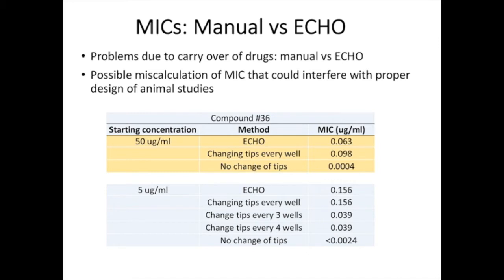And that can be significant, as you can see, for example, in this slide where there is a table. By the Echo, one compound looks to have an MIC of 0.063 microgram per milliliter. When we did it by hand, not changing tips, the MIC looked like it was 0.0004 microgram per milliliter, so a very significant difference. That could have a significant influence on running other assays, like testing compounds in animals, because a miscalculation of the MIC could interfere with the proper design of an animal study, and then with the conclusion that the compound might not be effective against that bacteria in vivo.